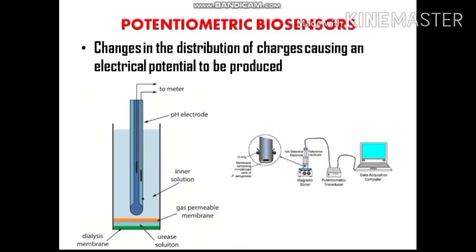Next is the potentiometric biosensor, which is based on changes in distribution of charges causing an electric potential to be produced. For example, to measure urea: urea crosses a dialysis membrane and reacts with a urease solution, producing ammonia and carbon dioxide. The carbon dioxide interacts with a pH electrode, altering the pH and causing a potential difference. The resulting electric current is directly proportional to the urea concentration and is fed to a digital display.